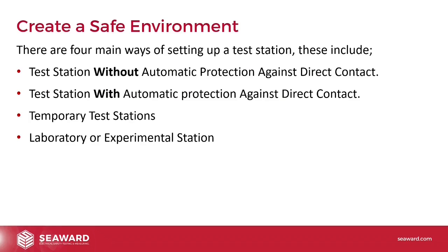So we're going to talk about mainly two of the four different ways of setting up a test station. The two we're going to talk about are a test station without automatic protection against direct contact and a test station with automatic protection against direct contact. You also get temporary test stations which need to apply all of the same factors that we're talking about today, so exclusion zones, warning signs, things like that.